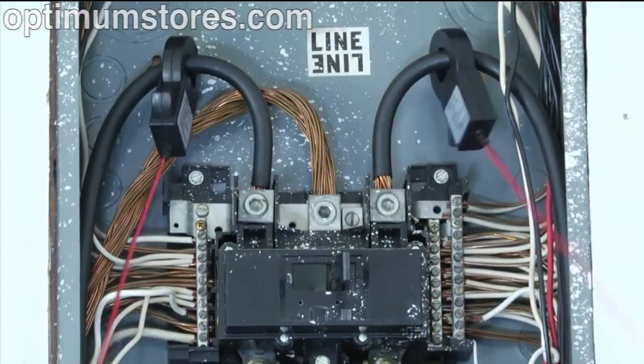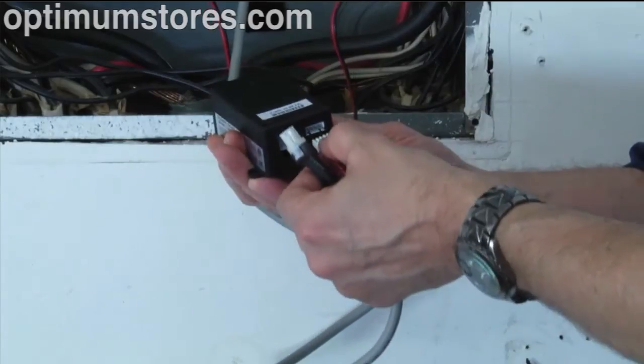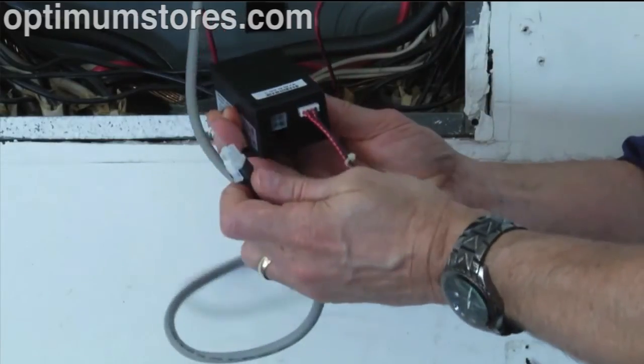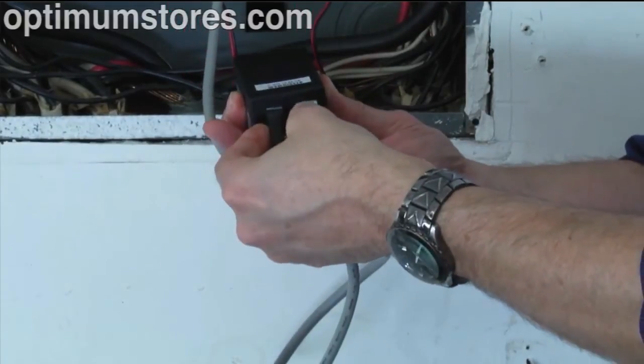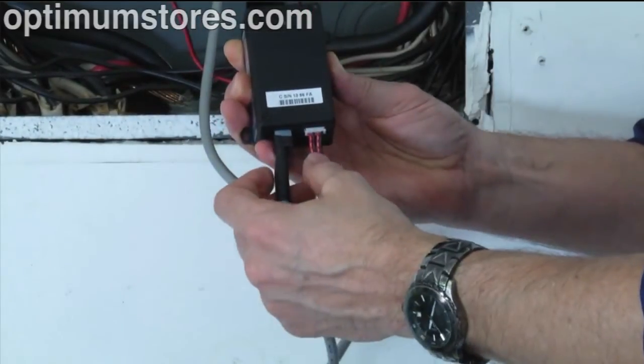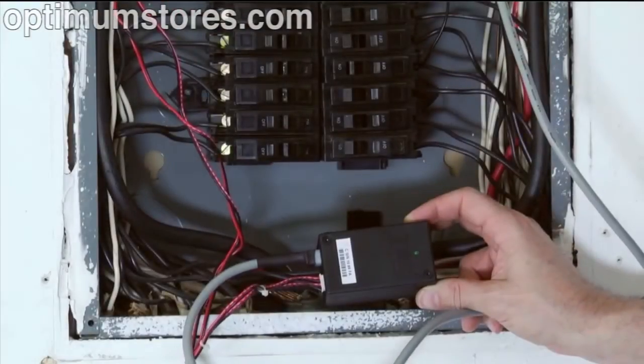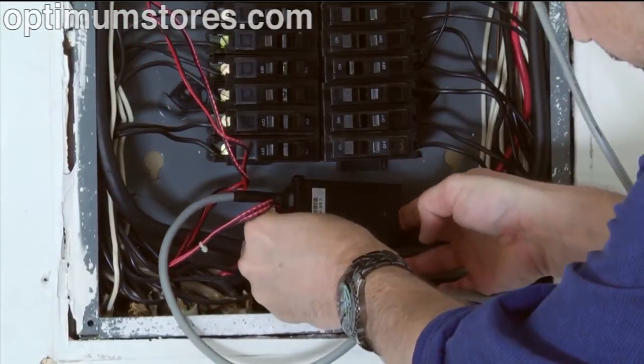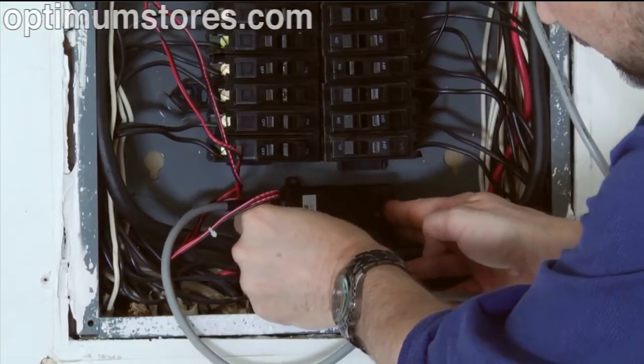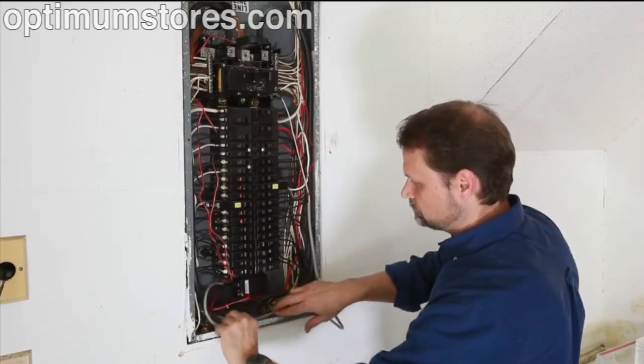Do not expect the CTs to fit tightly around the conductors. Connect the CTs and power cable to the MTU by plugging the plastic mating connectors together. Note that the connectors are polarized and can only be inserted one way — do not force. Next, determine the best location to mount the MTU, choosing a location where it will not interfere with existing equipment or wiring. Attach the MTU with double-sided tape if allowed in your jurisdiction, or with sheet metal or machine screws.